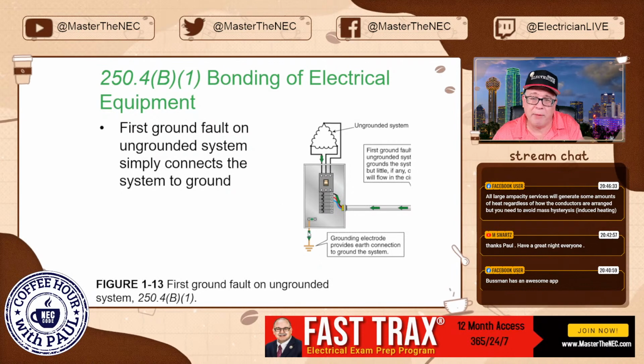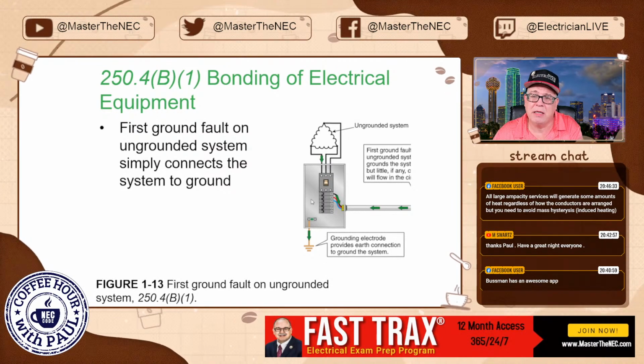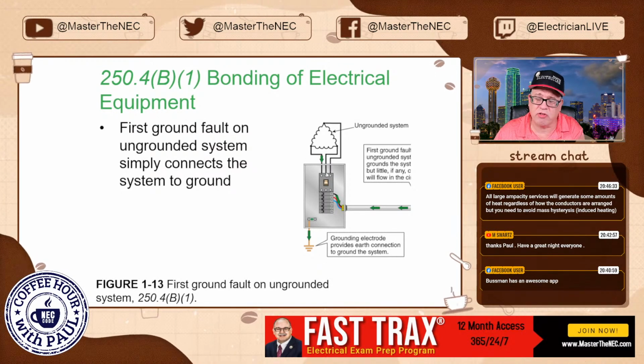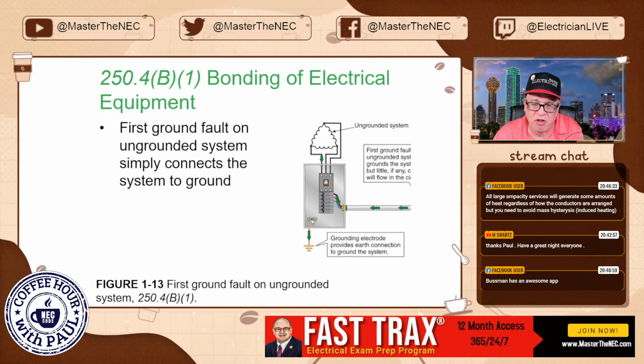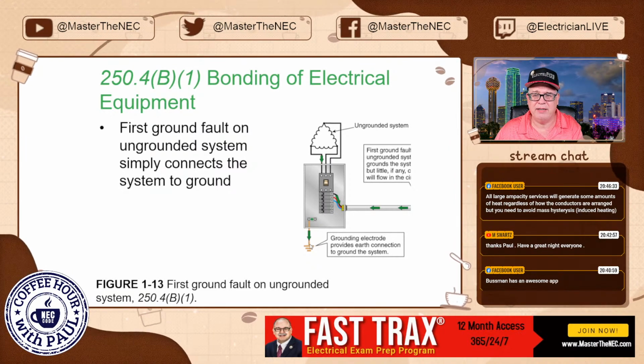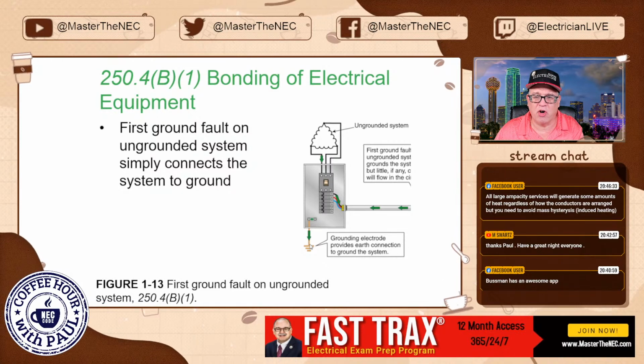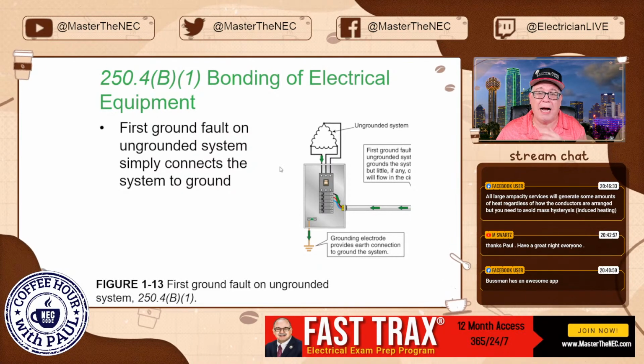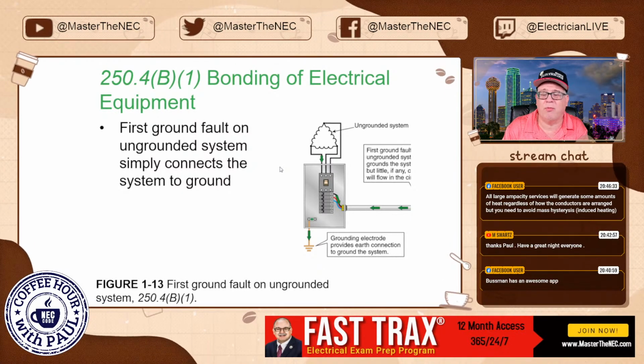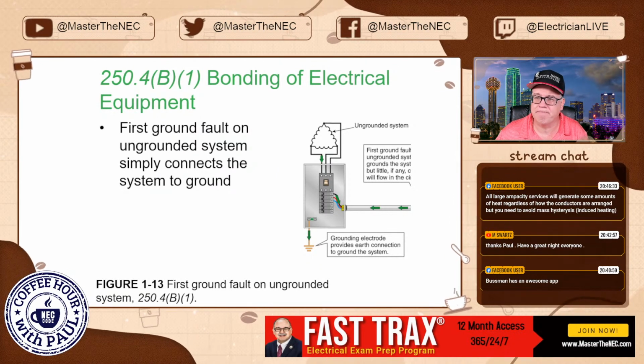But the point I want to make here is notice this cabinet. So this has no grounded conductor brought to it, but you notice it still has to be connected to earth, okay? The grounding electrode provides the earth connection to ground the system. Why? Because it told us that we had to do that, okay?